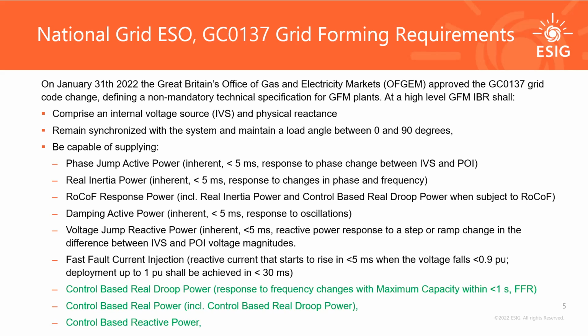Rate of change of frequency response power combines some of these responses together with controlled frequency response, which is more similar to how a grid following inverter can respond as well. Then damping active power, voltage jump reactive power, which is again almost instantaneous reactive power injection, and fast fault current injection. And then there are these 3 functionalities in green that are control based. I colored them green because I think grid following inverters are also capable of providing them. So I'm not really sure why these functionalities are called out in grid forming specifically. It would have been a grid following capability.